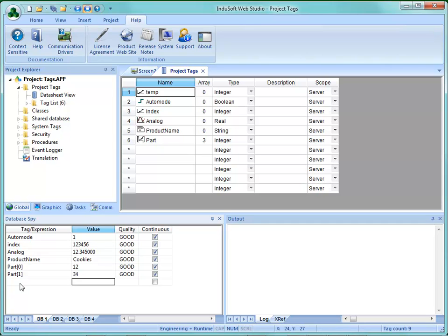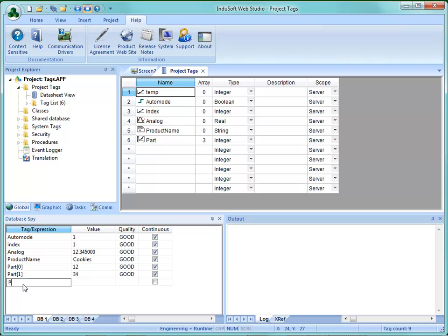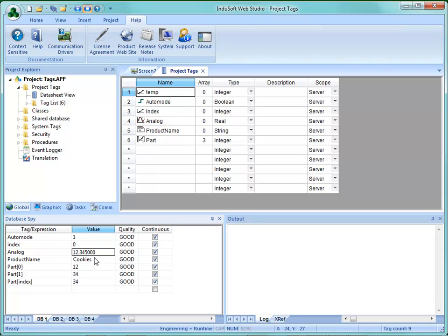You don't have to use just a constant as the array index. For example, if I choose Index as my element number, I could put Part with another tag name inside square brackets. Here I'm referencing element 1. If I change Index back to 0, it now references element 0. Another point: you can put simple expressions inside the brackets, but you cannot have spaces — so 'Index+1' will work, but 'Index + 1' with spaces will not.